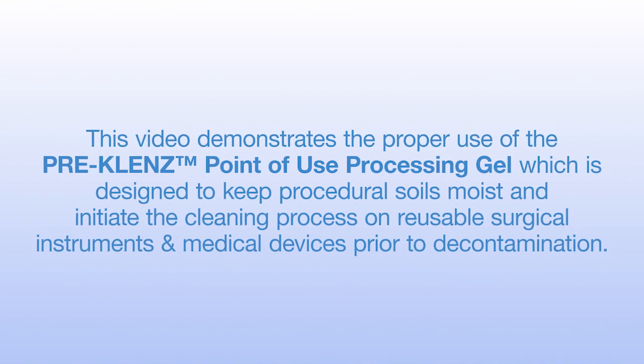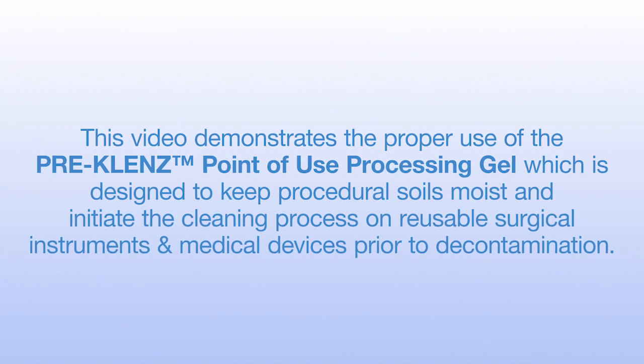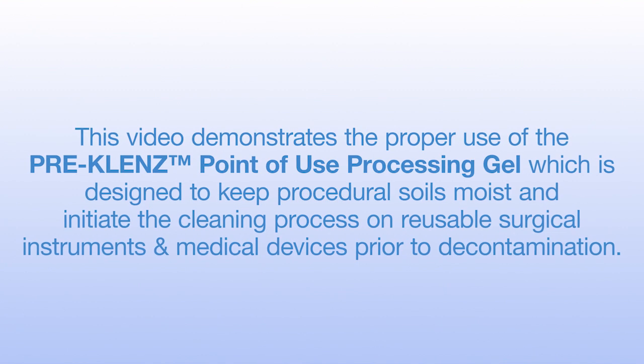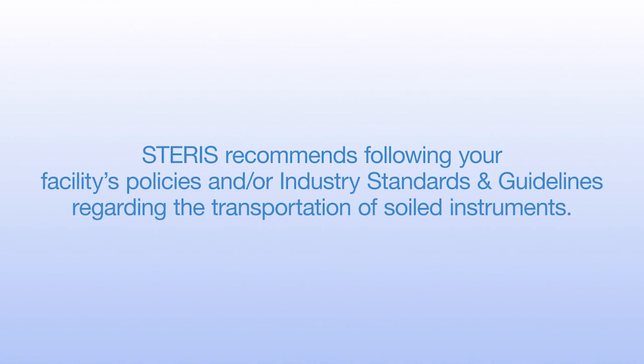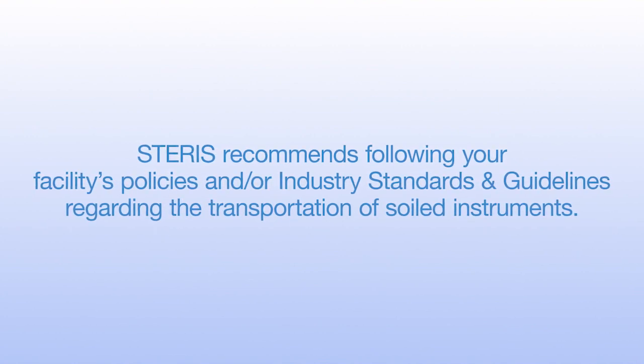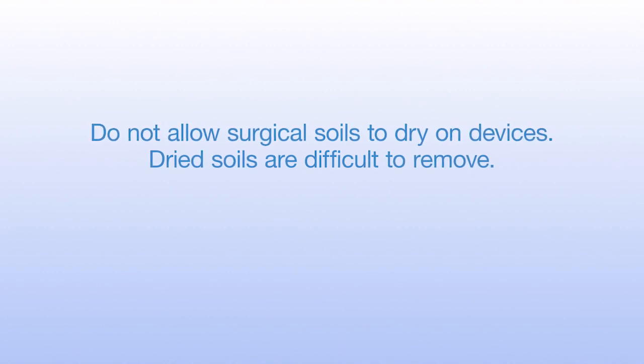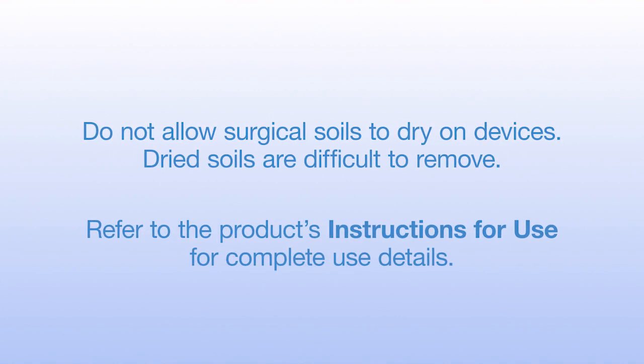This video demonstrates the proper use of PRE-KLENZ point-of-use processing gel, which is designed to keep procedural soils moist and initiate the cleaning process on reusable surgical instruments and medical devices prior to decontamination. Steris recommends following your facility's policies and/or industry standards and guidelines regarding the transportation of soiled instruments. It is important that surgical soils are not allowed to dry on devices before cleaning and reprocessing, because dried soil is much more difficult to remove. Refer to the product's instructions for use for complete product use details.